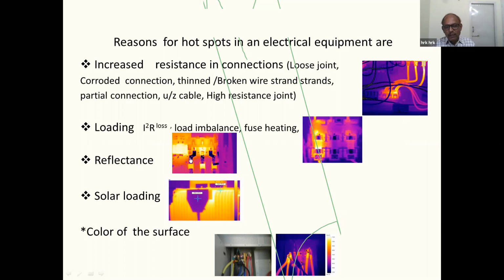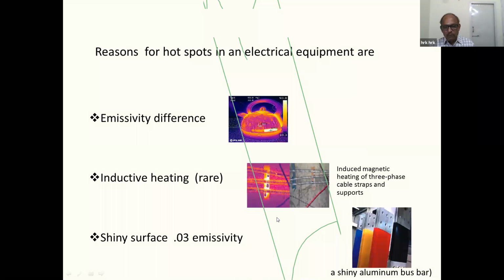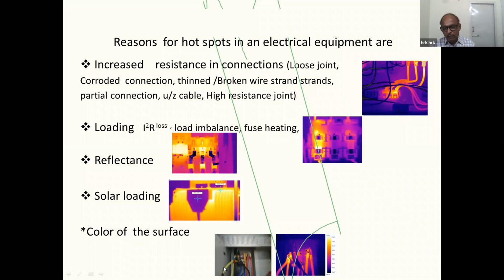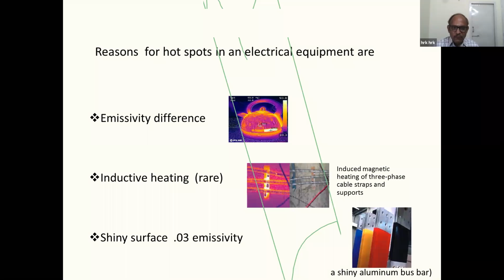Similarly, when we take thermography where there is no electrical supply or nothing is connected, there also we find a temperature rise. This is because of reflected temperature. Normally, when we do outdoor thermography, because of sunlight's reflection on the objects, we find the temperature is very high. Similarly, on a transformer outdoors, we will find this. Red and yellow are the hot colors, and the image will show as if it is very hot, but actually it is not hot. The black, gray and dull colors show no change. Another reason is if anything is blocking the infrared rays, then there will be a temperature variation on the surface.